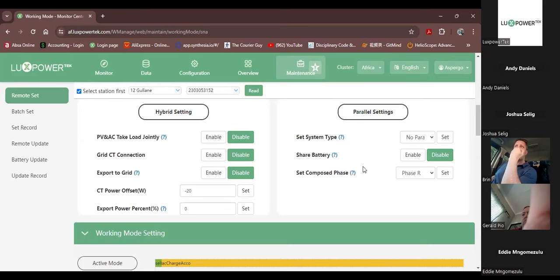If you work on the station and you switch the machines off for whatever reason, or you're doing firmware updates and you update one of the slaves first, as soon as the others go on and off, the first one to come back on again will reassign itself as the master. Careful: there's no reason that you should keep a particular machine as the master, but if for whatever reason you want to, you always have to make sure that machine gets switched on first when the reset starts.